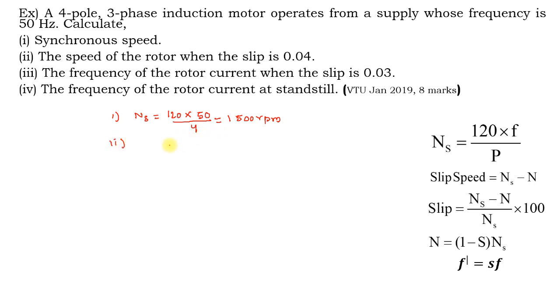The second one: find out the speed of the rotor. The rotor speed n = (1 − s) × ns, where slip s is given as 0.04 and ns is 1500 rpm. So the rotor speed is 1440 rpm.